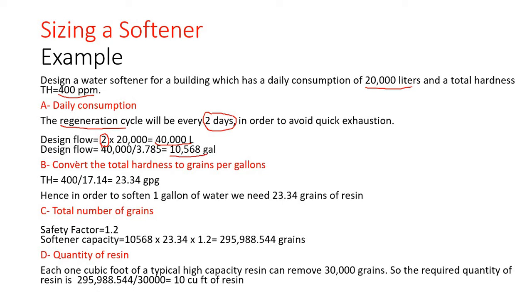Second, we need to convert the total hardness to grains per gallon. We will divide 400 ppm by 17.14, and we will get 23.34 grains per gallon. Hence, in order to soften one gallon of water, we need 23.34 grains of resin.